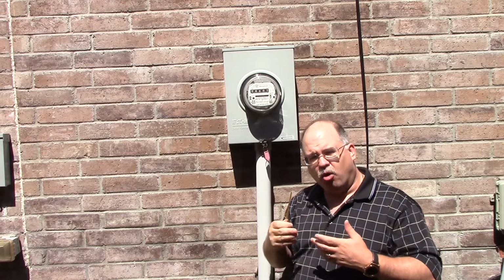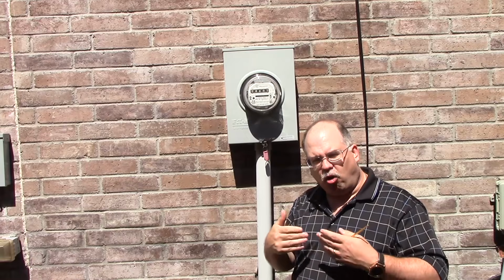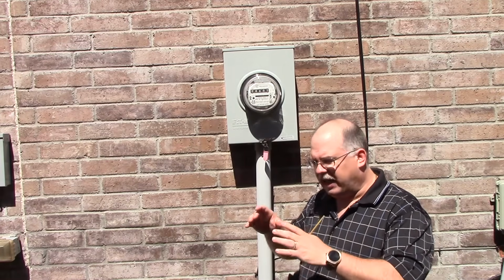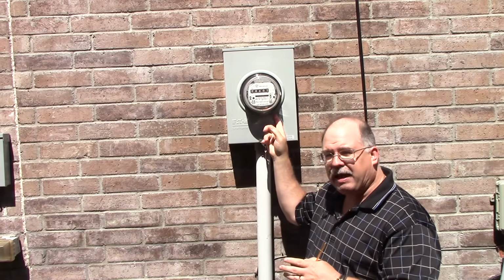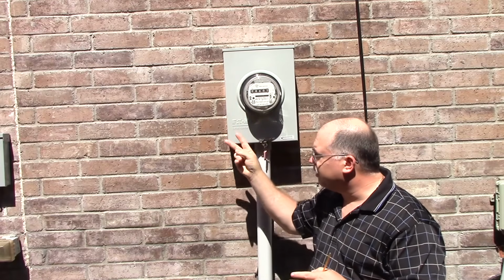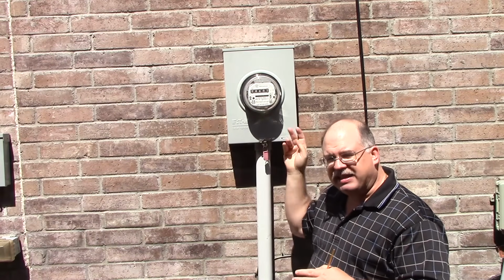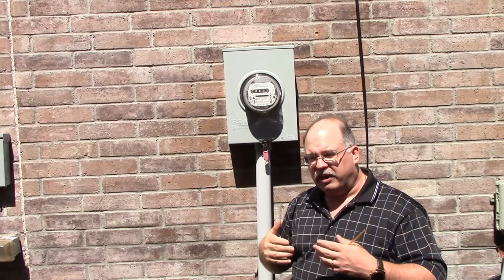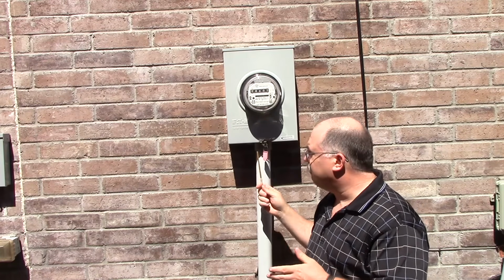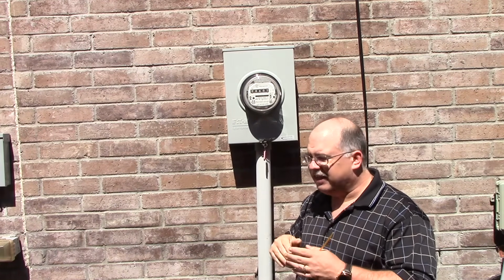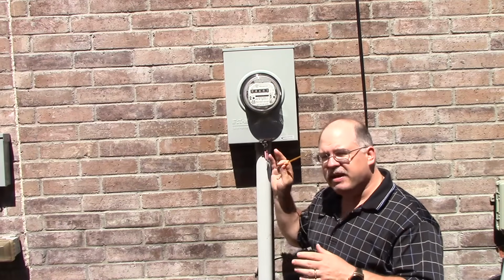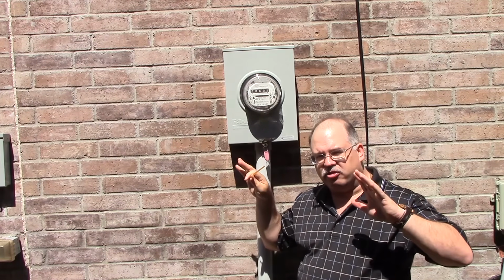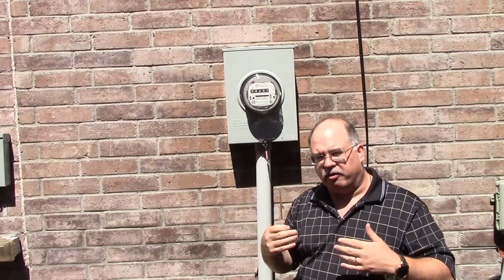rated meter, or it might even be a 30 in an old style you'd see back in the 30s, where it had the meter itself and a little flap here, and you saw the open conductors coming in and then going out of it. That was typical with an old style. When they started to get to the 60, you actually came in with some raceways. So again, that's how to tell the difference. But I'm never going to use that as my final determination, okay? The meter is really just confirmation.